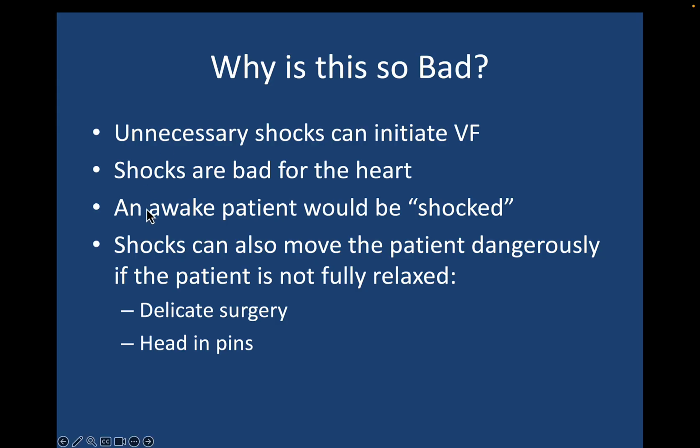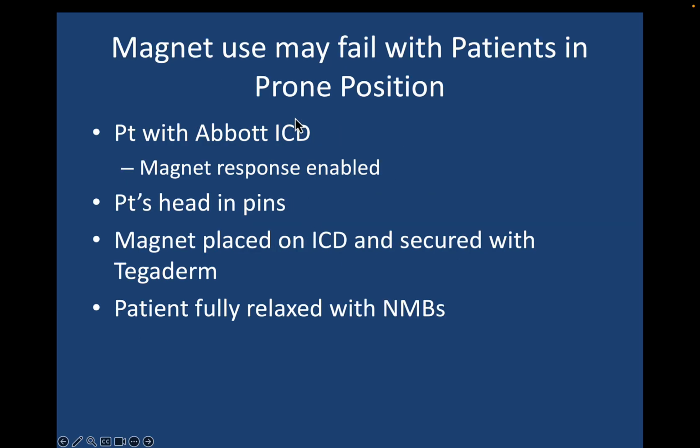Obviously, if this happened to an awake patient, the patient would be shocked and obviously mad. Shocks can also move the patient dangerously if the patient's not fully relaxed with muscle relaxants. This is particularly a problem if it's a delicate procedure, or if the patient's head is in pins and so on.